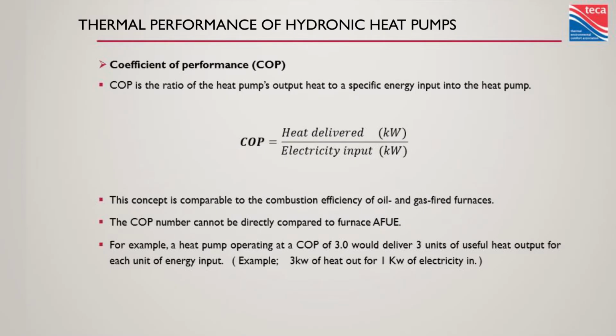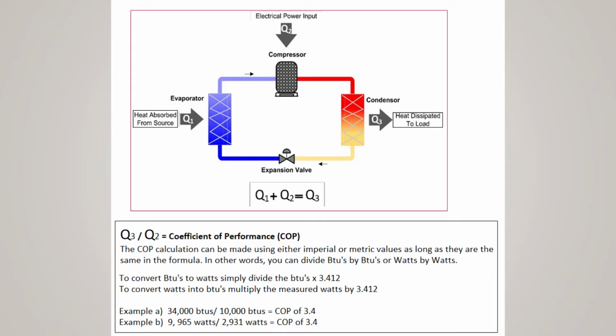So COP, I already covered this. Wattage out, wattage in. We get more out than we put in. Good job, everybody. So COP is how we measure these things. You can measure it quite easily. If you know what's coming out of that hydronic system through temperature difference and flow rate, you can calculate BTUs. You now know how much you're delivering. Simple to do with a couple thermometers or even some PT ports and some gauges you bring yourself. Now you've got your delta T. If you've got a pump curve and a couple pressure gauges, you can use that to calculate your flow rate.